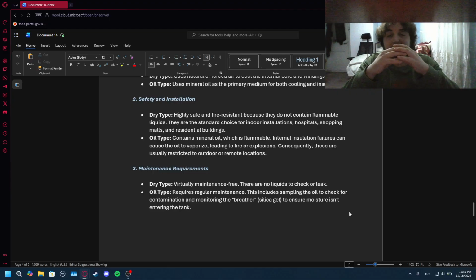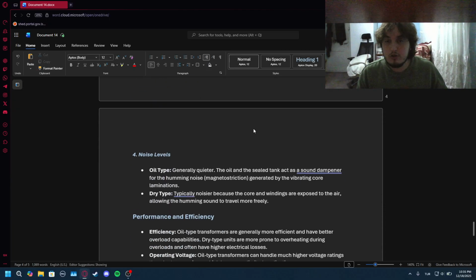All of these can cause fires. All of these can cause big problems. And do we want that? No, not really. Why would I want to waste my money? But here's the catch with that. That regular maintenance is basically to check the oil and to see if oil has vaporized inside of it. Because other parts are usually fine, but oil might vaporize, and that is usually the bigger concern when it comes to oil type transformers.